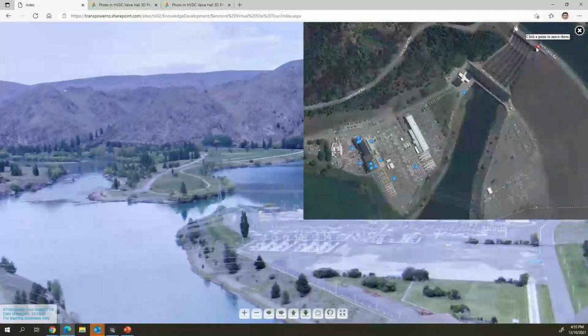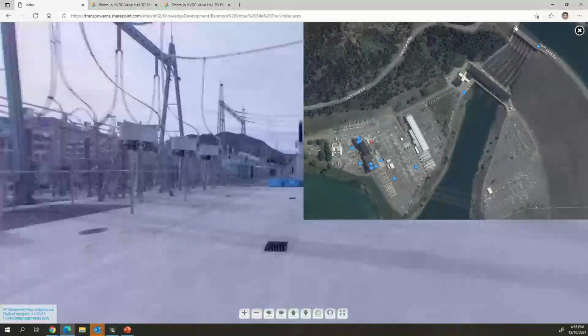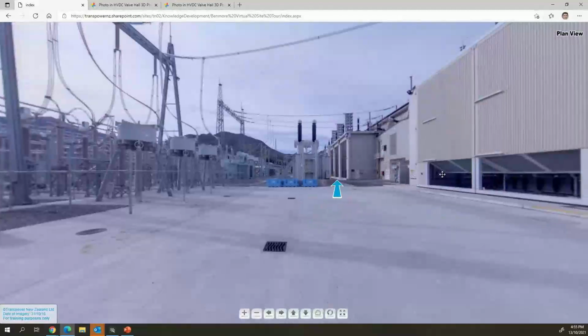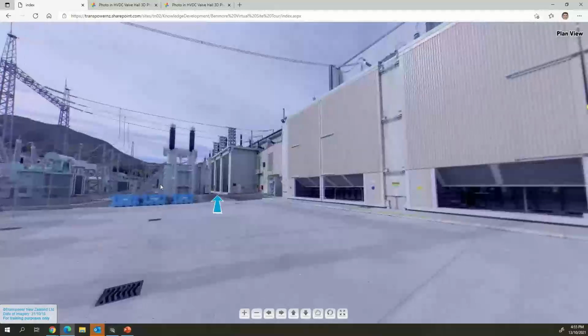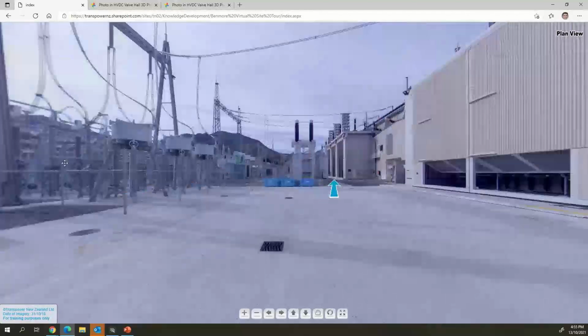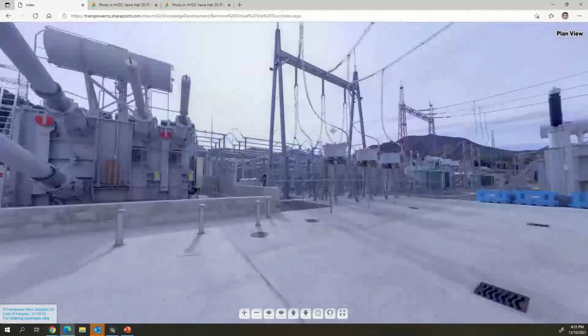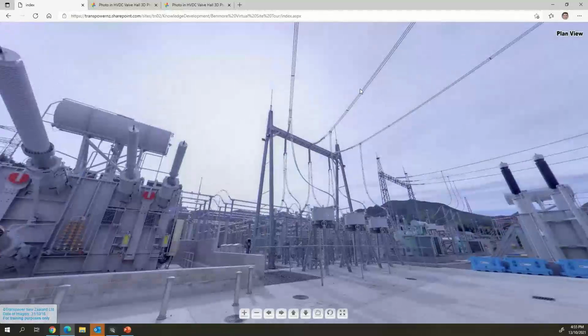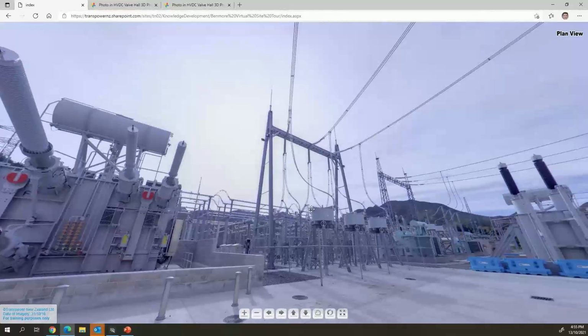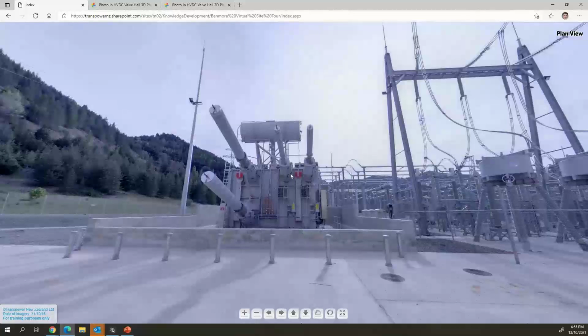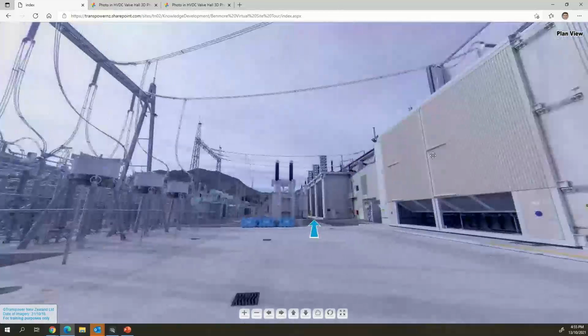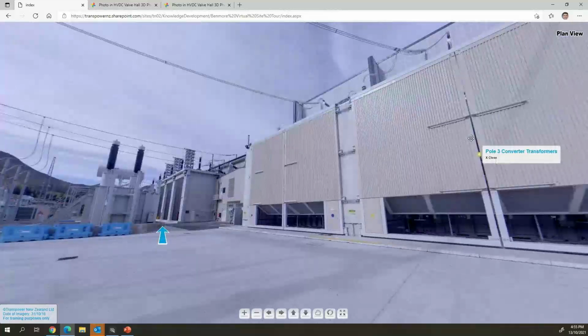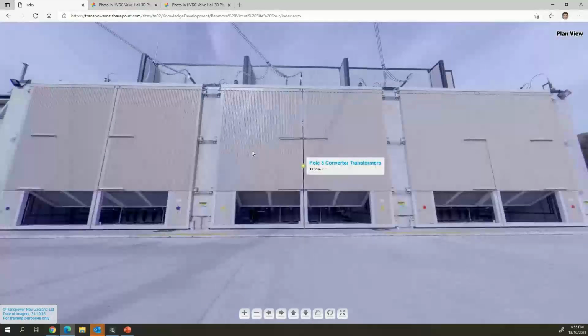We'll go down to pole 3. We'll start on the AC side of the converter and go over to the DC. So you can see this is our AC connection coming in here, 220 kV, 3 phases, red, yellow, blue. This is the spare converter transformer. As I said before, we've got the single phase 3 winding transformers. So this is the valve star and the valve delta is the small bushings. And the converter transformers fit in these bays here. We've got these doors on, so you can't see them very well, but they're in there.